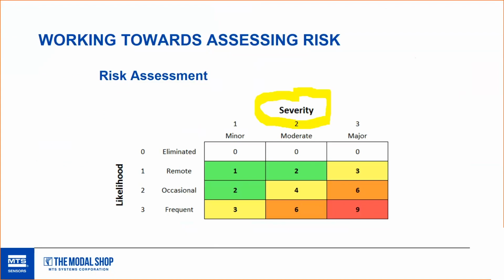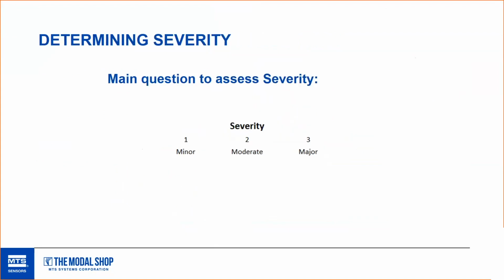So a modern approach really takes a look at both. Kind of start boilerplating this, making a simple business graph. In relation to calibration, if a measurement's made only to discover later that the sensor or your measurement channel was bad, what's the cost of invalidating that data or retaking it, if it's even possible? The answers to outcome or the severity range from low to extremely high cost of failure, and they form the other important axis in the risk assessment plan. And I want to go over a few examples to illustrate this point.